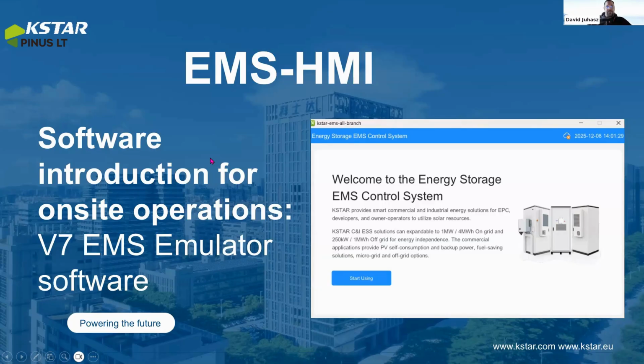And on the EMS, we see the versions. On the third page, we see the actual alarms. For troubleshooting purposes, this is the first page we need to help you out. And we have the alarm log, what happened in the past, and what operations we did with this equipment. And we have the settings, which are mostly used in the commissioning.